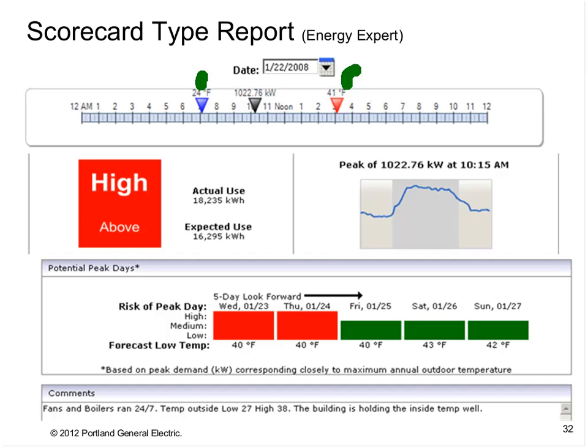This gray part right here, this thumbnail, is actually a good indicator of, I'd say, your schedule. Each gray line represents the start of your day and the stop of your day. So it looks like on the left side, they started up on time, but as far as ending when they should have, their hours of operation, it actually extended. So they didn't shut down like they should have. So that might have cost them a little bit extra than normal.